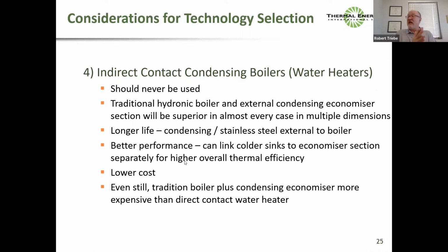Okay. And so indirect contact condensing boilers, again, now we're with, as I said, water in the tube and the flame on the outside. That two-stage thing, as I said, you can actually get better performance by separating the hydronic boiler and the economizer, and lower cost. And I'm going to describe why. So it's more cost effective, it lasts longer, and it gives you the opportunity to be more efficient.